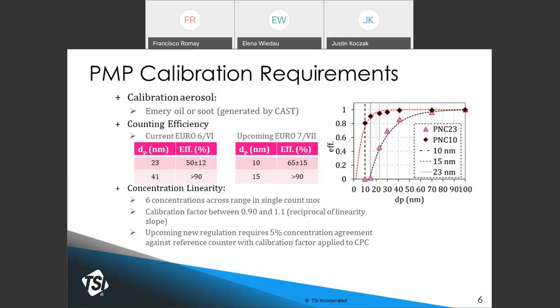In addition to counting efficiency in the steep part of the curve, these CPCs need their concentration linearity checked, typically done at six different concentrations in single-particle counting mode. The calibration factor for the linearity curve should be between 0.9 and 1.1, and this linearity factor is the reciprocal of the linearity slope. For upcoming Euro 7 regulations and 10-nanometer CPCs, after applying the calibration factor, the requirement for concentration agreement between the CPC and reference counter is 5 percent.